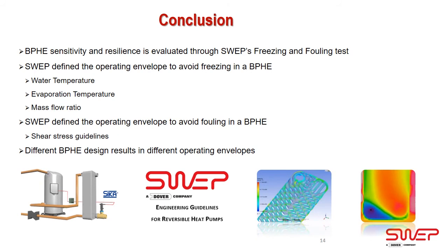As a conclusion for the project, we have been evaluating BPHE sensitivity and resilience through SWEP freezing and fouling tests. From our tests, we can now clearly define the comfort zone of the SWEP brazed plate heat exchanger in regards to freezing, based on the water temperature, evaporating temperature, and mass flow ratio. Also, we defined guidelines about minimal shear stress value for various water qualities in order to minimize the risk of fouling. Based on that, we have been able to improve the design of our BPHE in order to make them more freeze resilient and less foul sensitive.